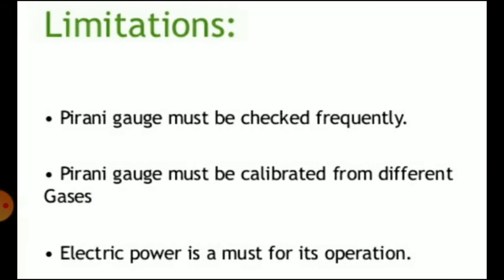Now limitations. Pirani gauges require calibration against some pressure standards. Pirani gauges must be checked frequently. Electric power is a must for its operation. Then the transient response of Pirani gauges is poor.